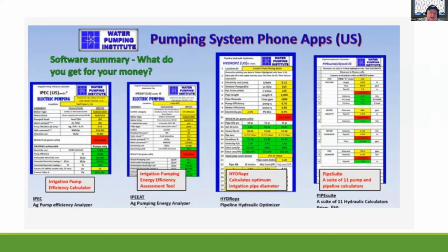What that comes with is 4 software suites, one of which is the pumping tool that I showed you that he gives away. Then he also has an assessment tool that ties it back to the actual pump in further detail, with additional on-site tests that he recommends you take. Then he's also got what they call HYDROpz. You can probably jump in and say the names, Rob. Basically, it lets us look at the pipe diameters, because I was flabbergasted by the difference in even just a 10-inch to an 8-inch pipe over a long distance, with the Hazen-Williams loss factor, because the pipe was older, and how much loss was happening just in the pipeline.